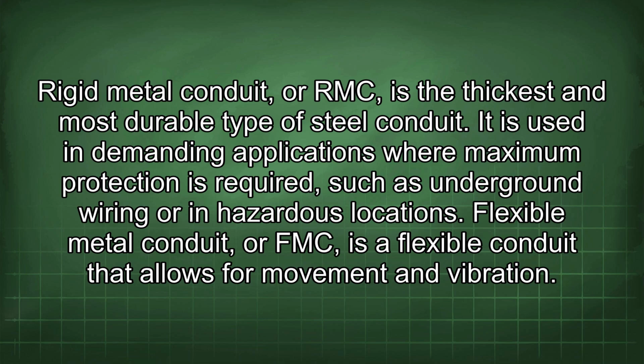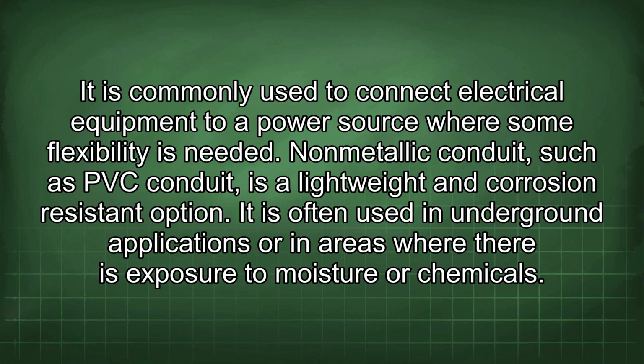Flexible metal conduit, or FMC, is a flexible conduit that allows for movement and vibration. It is commonly used to connect electrical equipment to a power source where some flexibility is needed. Non-metallic conduit, such as PVC conduit, is a lightweight and corrosion-resistant option. It is often used in underground applications or in areas where there is exposure to moisture or chemicals.